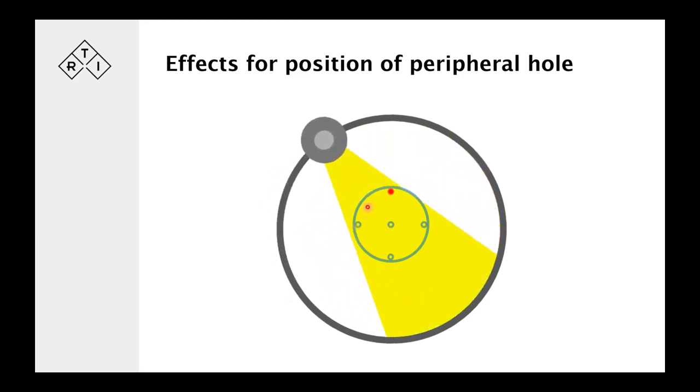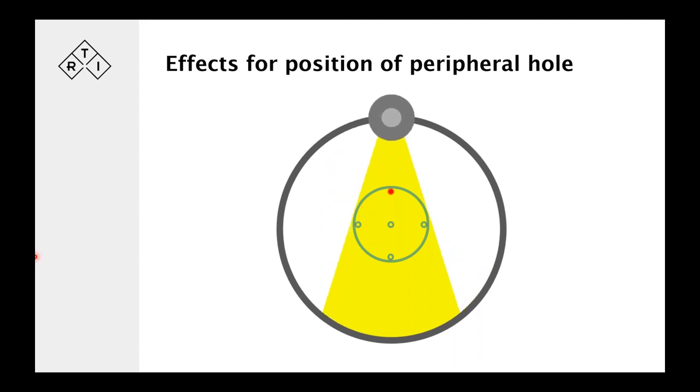So we'll have a non-constant dose in the peripheral holes. If it's in the center hole, of course, it's symmetrical, so we should have a constant signal output from the pencil ion chamber. In the peripheral hole, it will vary depending on the position of the tube, and of course that has to do with the distance and the dose rate in that measurement situation.